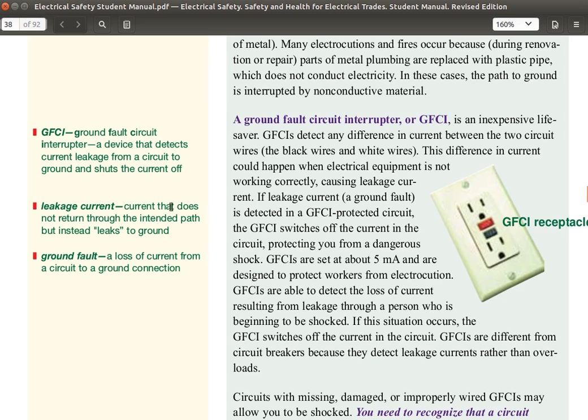Leakage current is a current that does not return through the intended path but instead leaks to ground. And it could be leaking from the person's hand through their body, down their feet and to the ground. Ground fault is a loss of current from a circuit to a ground connection. GFCIs are able to detect the loss of current resulting from leakage to a person who is beginning to be shocked. If this situation occurs, the GFCI switches off the current in the circuit.